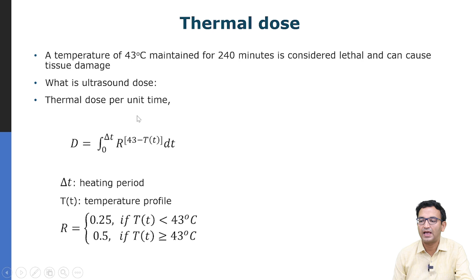So, we define a concept of ultrasound dose. The thermal dose per unit time is defined as D, and it is given as an integral over time of R to the power (43 minus T of t), where T of t is the temperature profile, and R is given as 0.25 if the temperature is lower than 43 degrees, and 0.5 if the temperature is greater than 43 degrees. Delta t is the heating period and T of t is the temperature profile. Now, this is an empirically derived formula. It is not derived from first principles, but it is useful in terms of calculating the thermal dose per unit time.